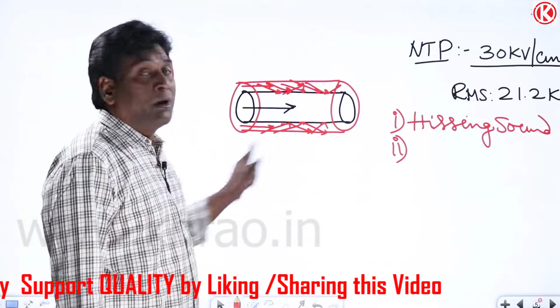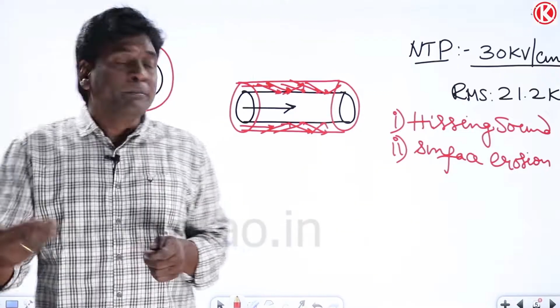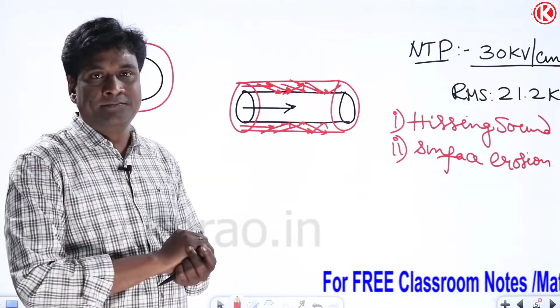We will be able to hear a hissing sound. Now, because of bombardment of ions around the surface, erosion will definitely be there on the surface of the conductor. Meaning that while installing the transmission line, the surface of the conductor can be smooth, but over time, because of this erosion, the total surface of the conductor will slowly become rough due to corona.